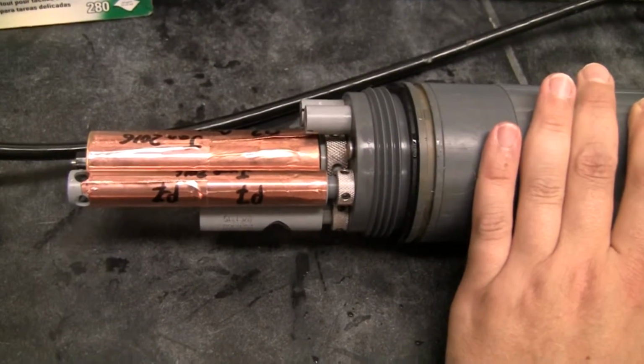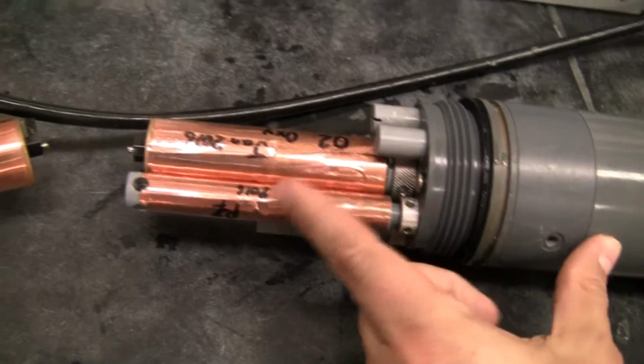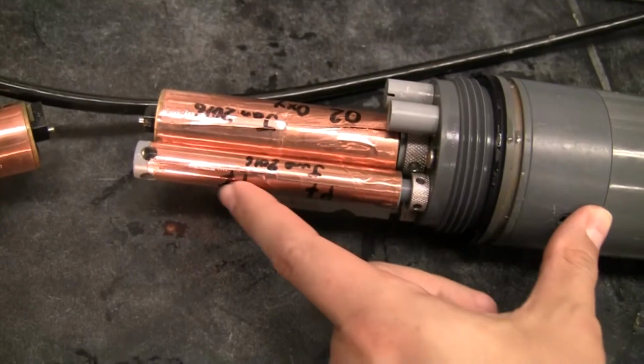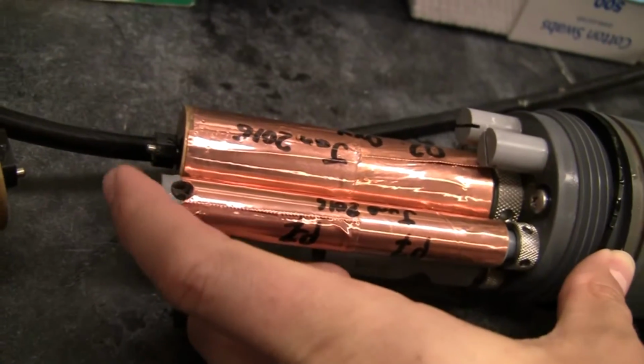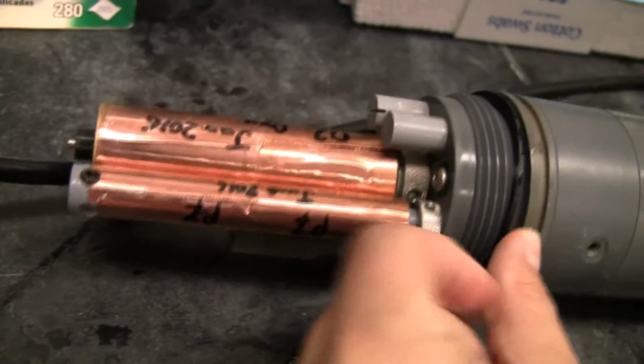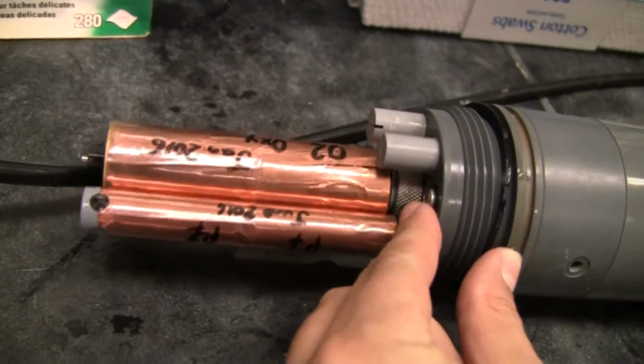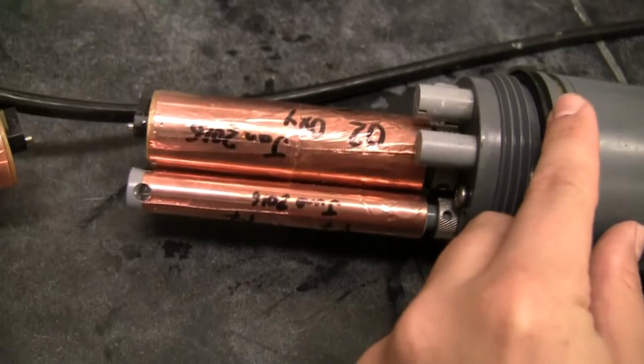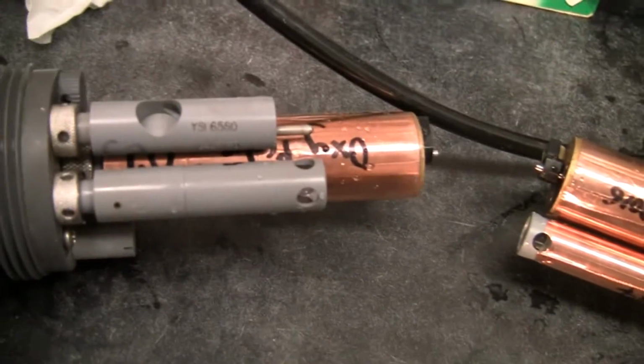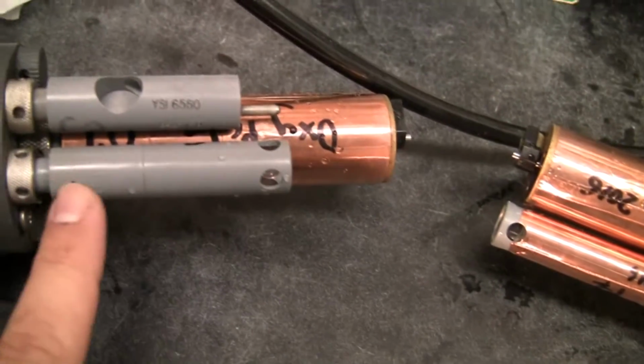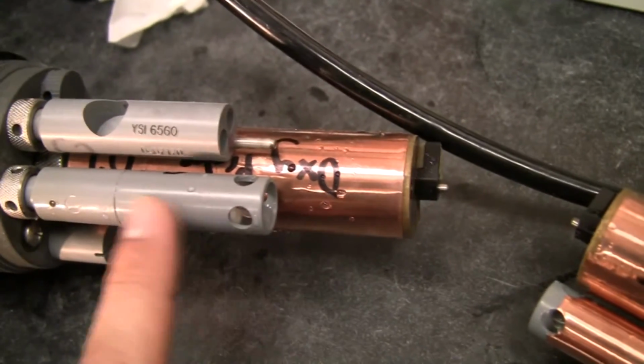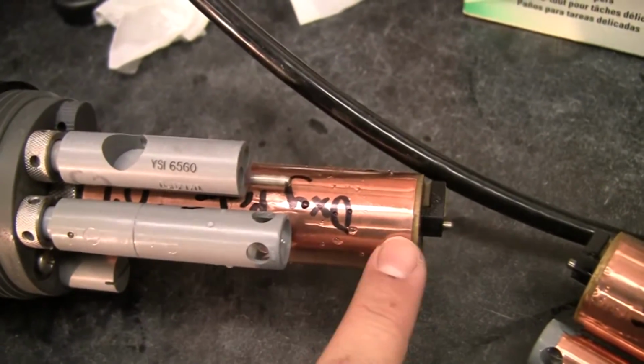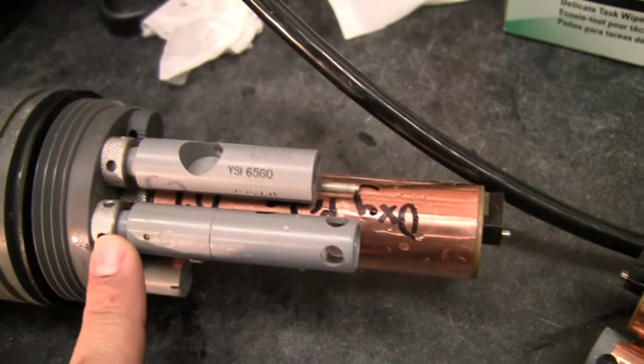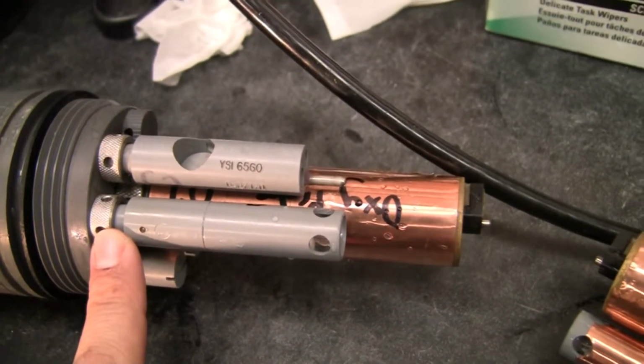So now we're ready to calibrate the pH probe. On this unit, this is a very long pH probe. It's a double length probe, but it has a small, looks like a little light bulb, at one end. This one is wrapped in copper as well for anti-fouling. For another example of a pH probe, this is a standard length pH probe, which again comes out of the smaller port with the light bulb at the end. So this is what they look like right here. They're optical, but they don't fit in the large port. They fit into the smaller ports of these YSI units.